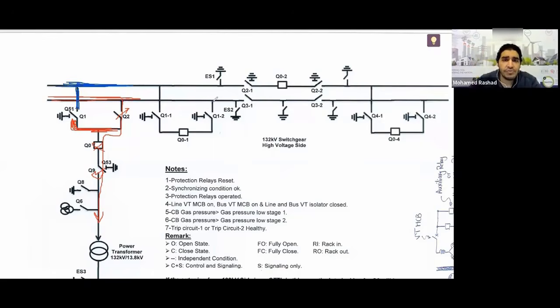Now connect the red voltage from here, and when I come to close this disconnector, it will connect the red voltage up to this point, right? Also, connect the voltage, which is in blue color, down to here. Close this disconnector, and it will connect the voltage here as well in blue color. If I come and perform synchronization by comparing the voltage of the VT of the bus coupler and the bus bar, and the circuit breaker is closed, what will happen? The two voltages will now be aligned with each other with the same voltage.